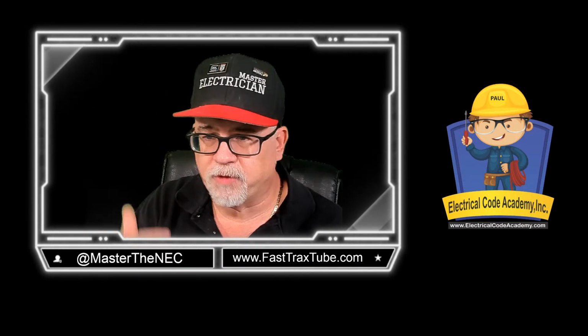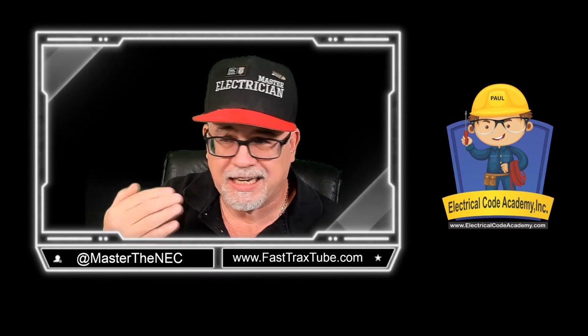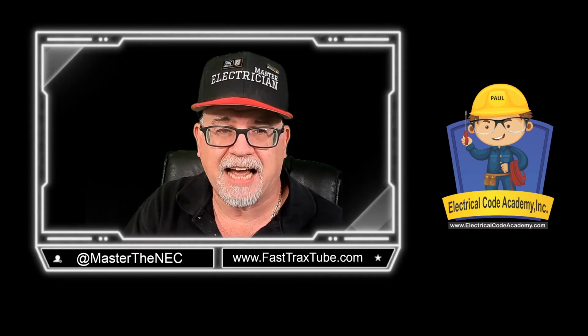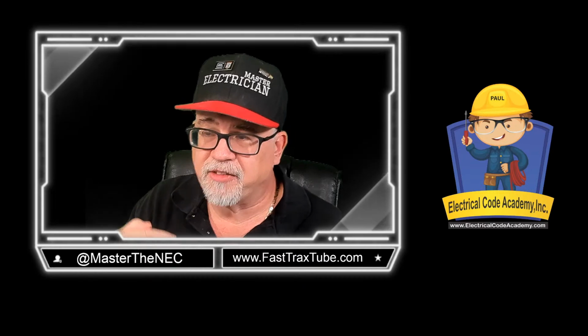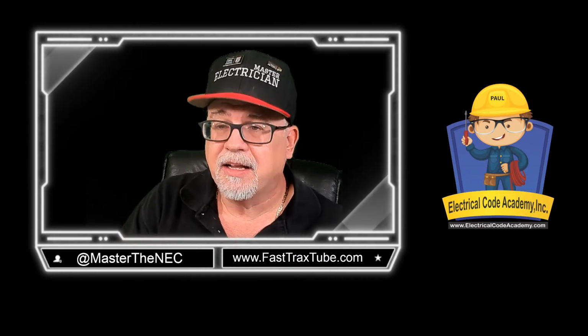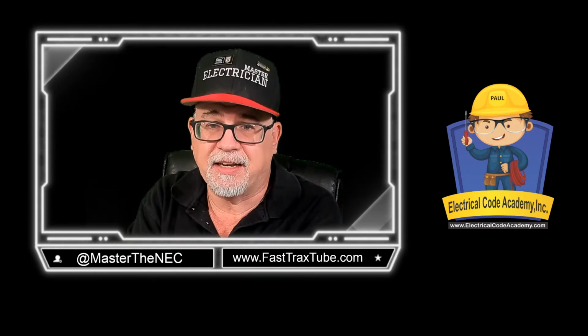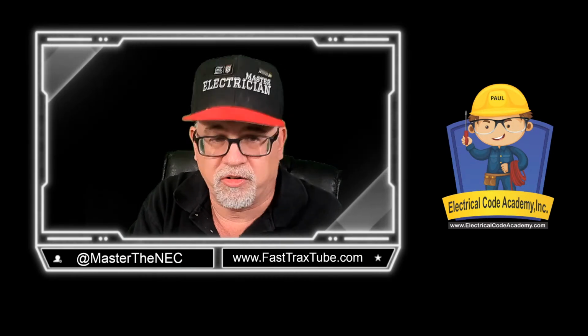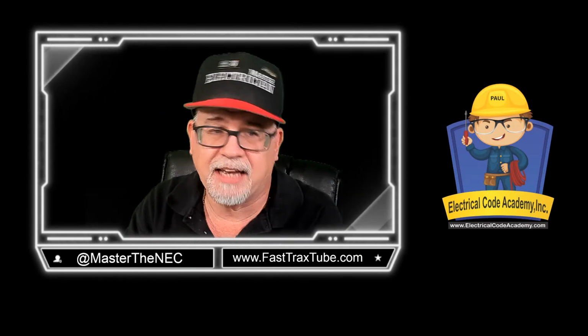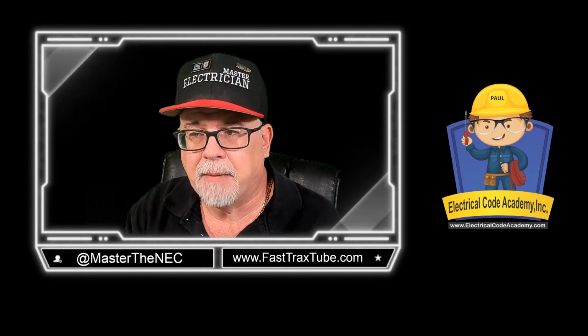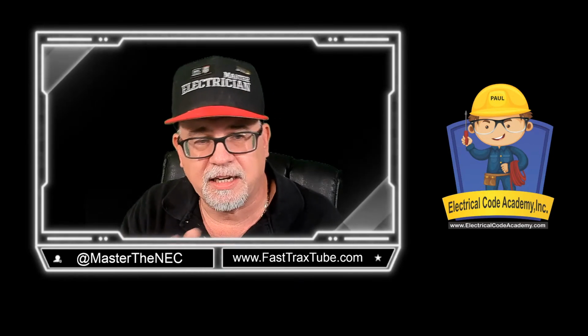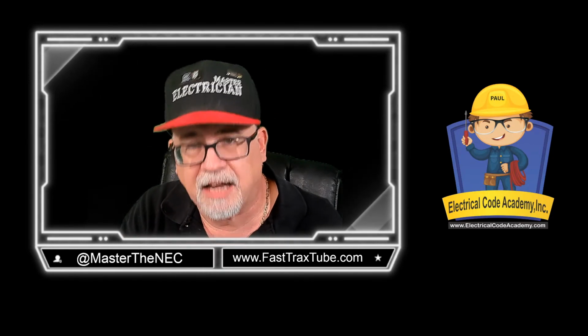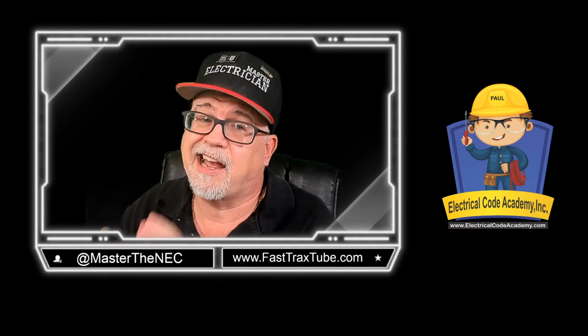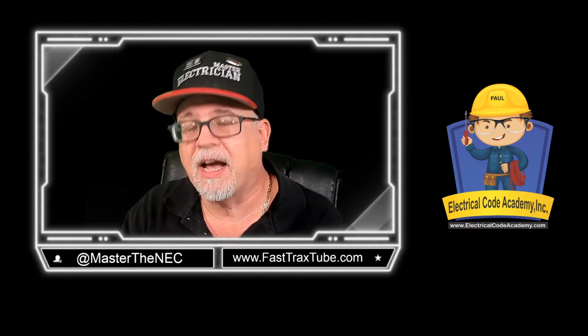Just remember, if you're doing a receptacle replacement in a location that now requires GFCI and it didn't then, or it requires AFCI and it didn't then, you're going to have to put in and protect it with AFCI or GFCI. Okay? And we'll cover that in a different video if that's confusing. But we really just wanted to talk about the ability to go from an old 2-prong style to a newer grounded type 3-prong and what the options are that you have.